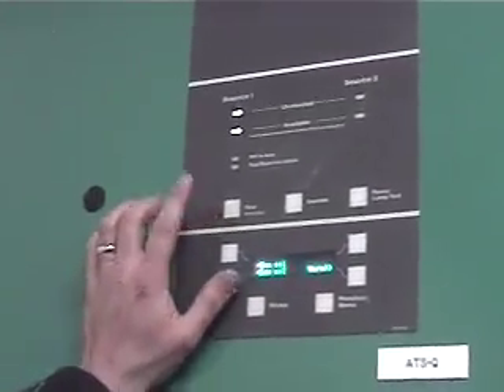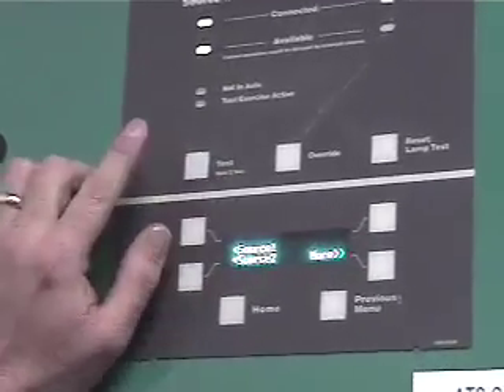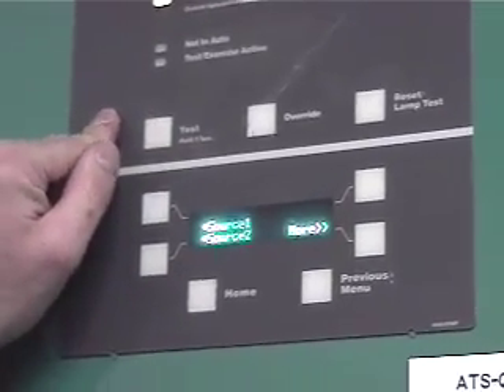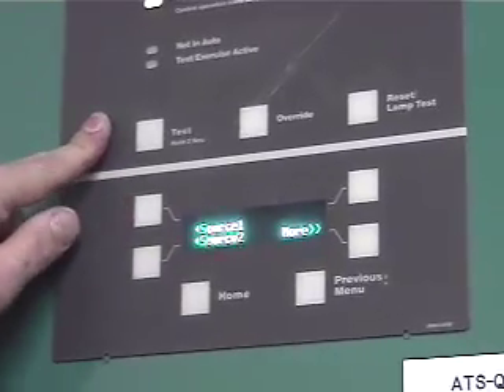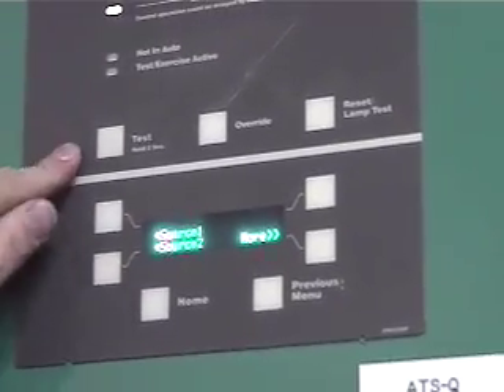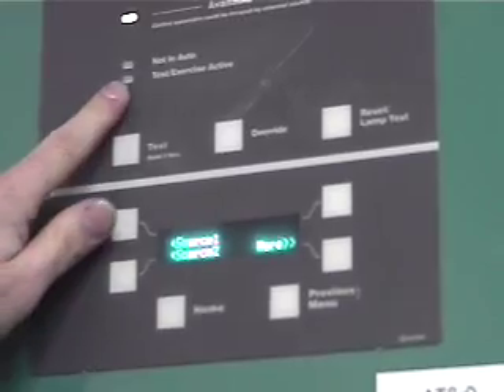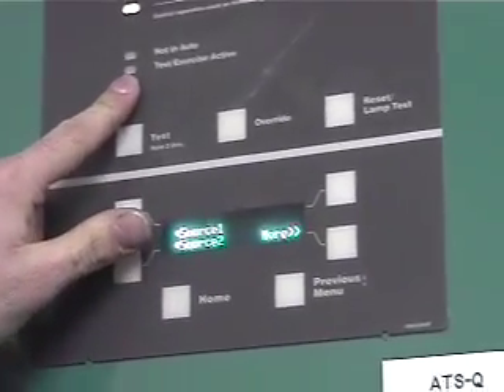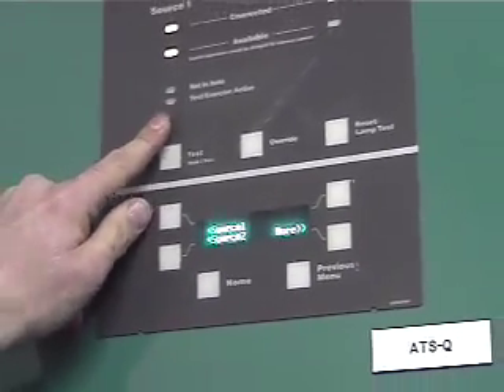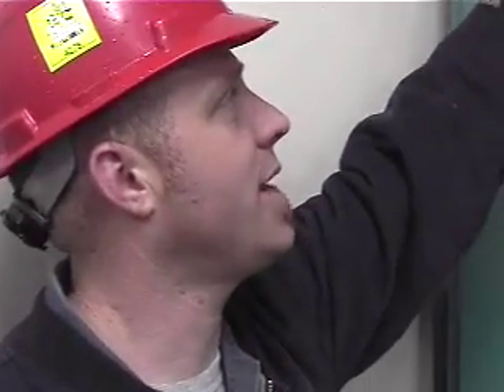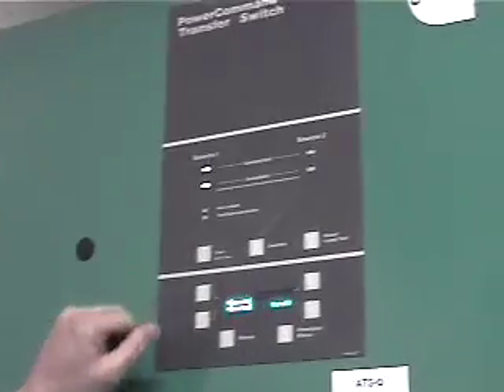Now, to do a test, you push and hold this in. It says for 2 seconds, but everybody's 2 seconds is different, like everybody's 2 inches is different. So if I'm going to do a test, I'm going to push and hold this test button in until this test light comes on and stays on solid. As soon as I push it in, it's going to start to flash. It's saying I'm getting your signal, but you continue holding it in until that light comes on solid. At that point, once it comes on solid, you can go ahead and let off. You'll see on the display, it'll start going through some timers.